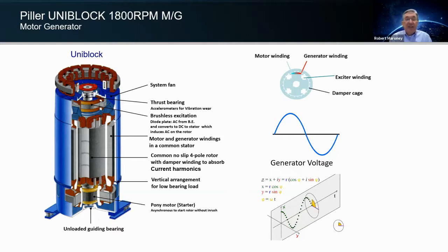The benefit of the pony motor, because this is a fairly substantial electric motor, is that we don't have to oversize the input breaker system, because the pony motor allows us to bring it up to speed very quickly without having to increase or overload that front bearing. So this gives you an idea of what this machine does and how it's configured. Inside the UPS, it would be about 2.5 feet in diameter and about 4.5 to 5 feet tall. So it's a large electric motor that stands vertically on bearings for reliability.